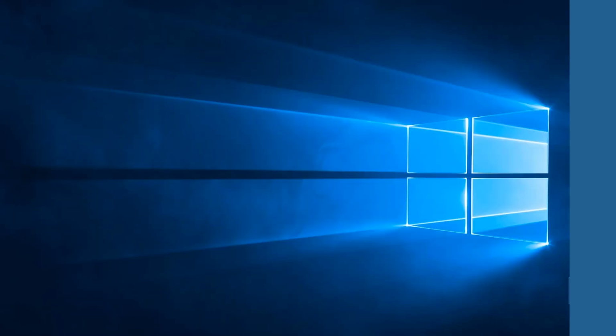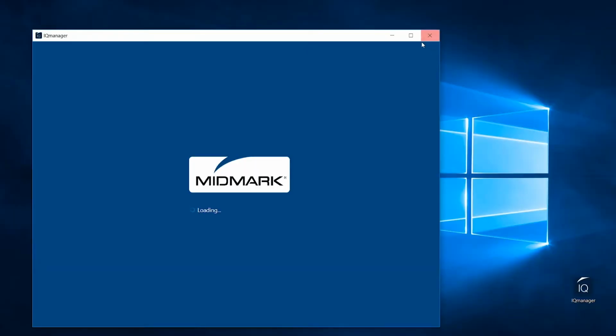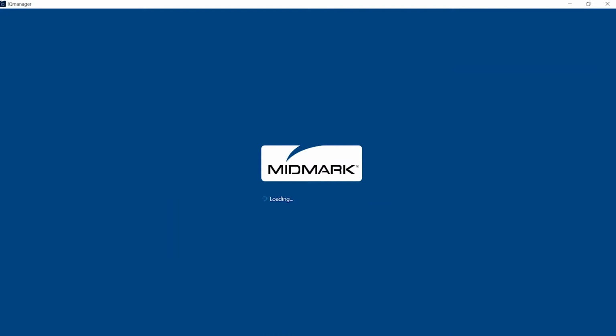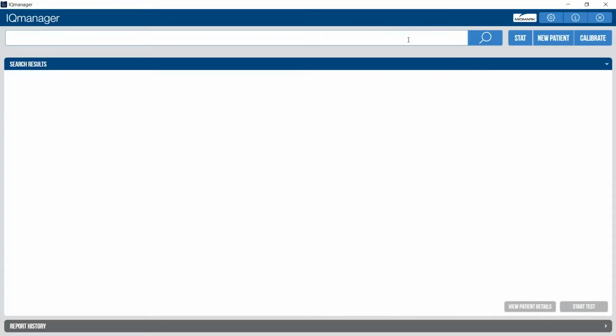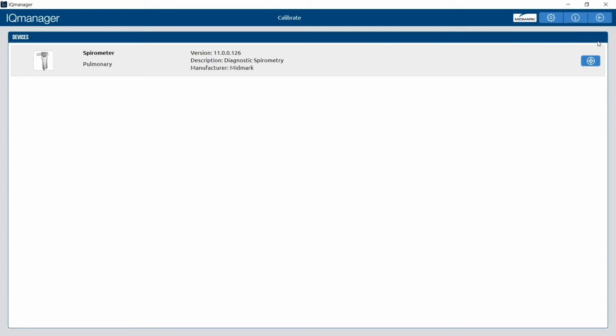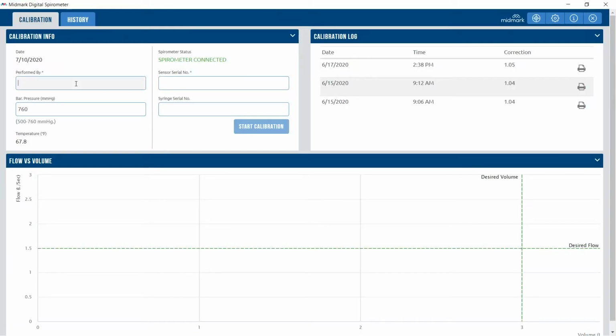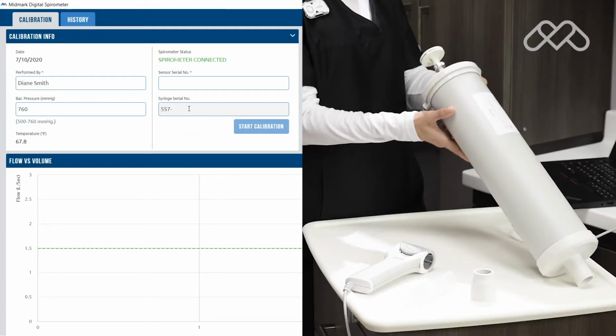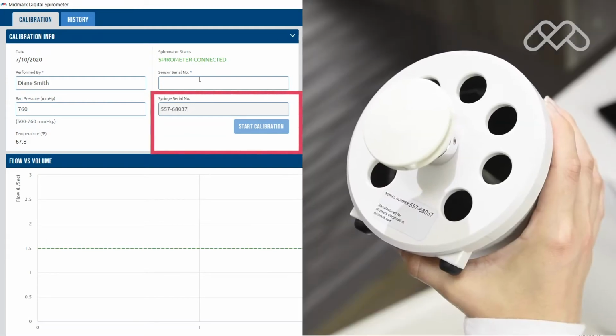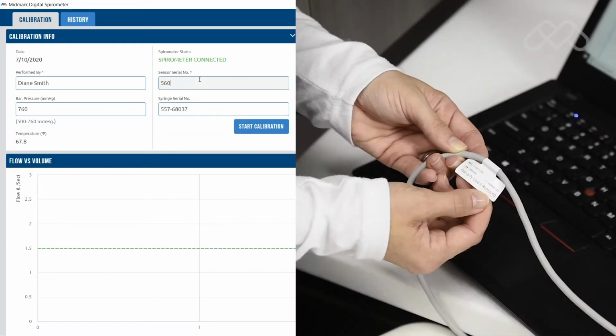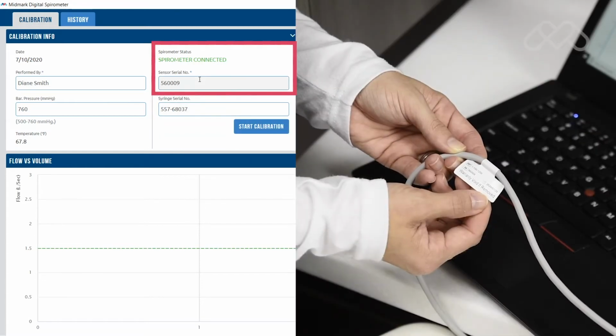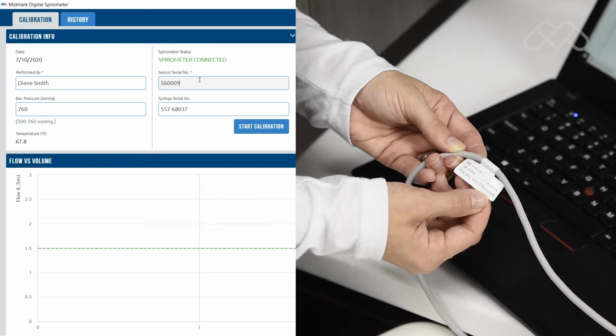Open IQ Manager by double-clicking on the IQ Manager icon on the computer desktop. From the operating software screen, click on the Calibrate button and choose the spirometer device to calibrate. This will take you to the calibration screen. The first time you calibrate your digital spirometer, the following information needs to be entered into the appropriate boxes: the user performing the calibration, the syringe's serial number, which is located on the handle end of the syringe, and the digital spirometer serial number, which is located on the label of the device.